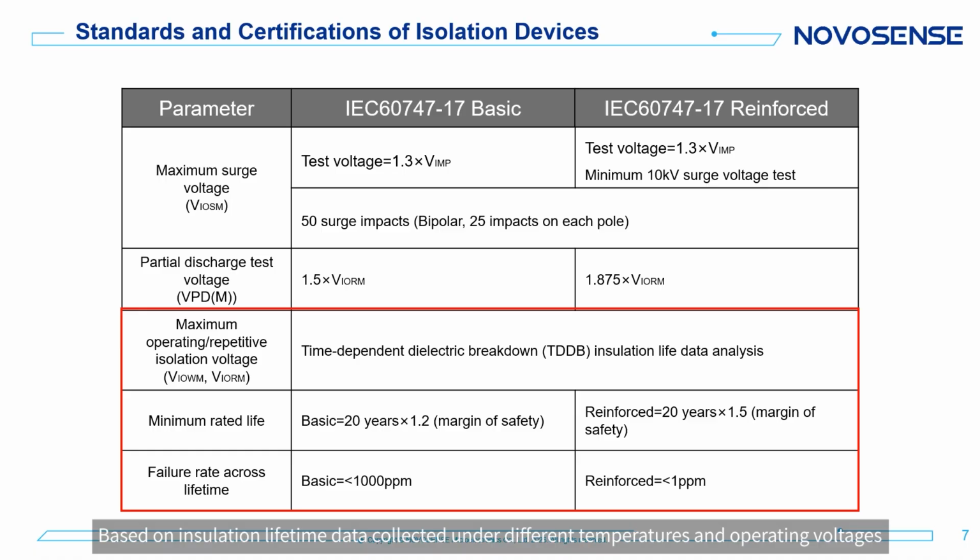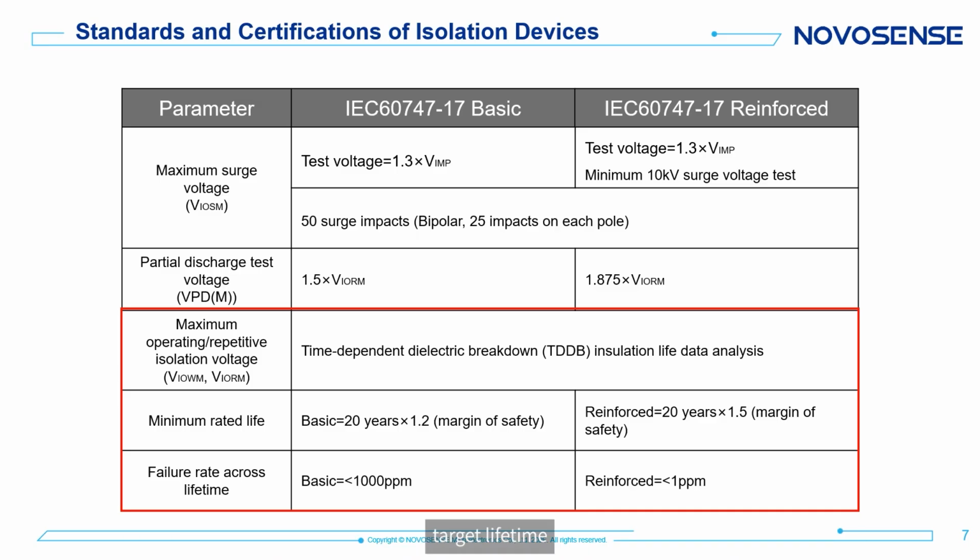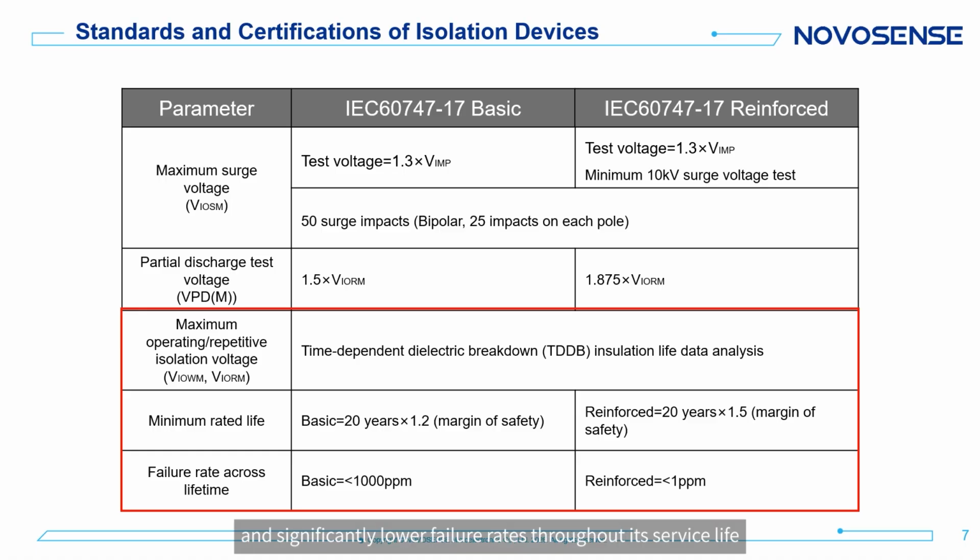Based on insulation lifetime data collected under different temperatures and operating voltages, Weibull distribution analysis is used to model the relationship between operating voltage, target lifetime, and failure rate. Combined with VDE-defined coefficients, VIOWM and VIORM can be derived. As shown, reinforced isolation provides longer operating lifetime and significantly lower failure rates throughout its service life. Once these tests have been successfully completed, the device is considered to meet the requirements for VDE certification.